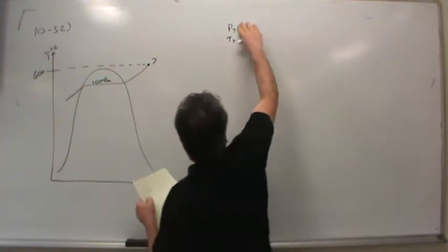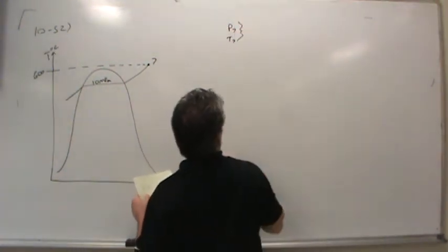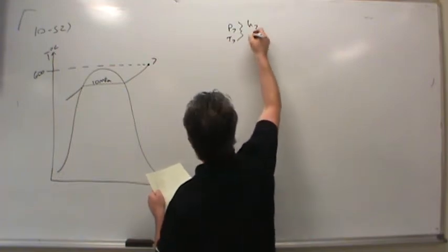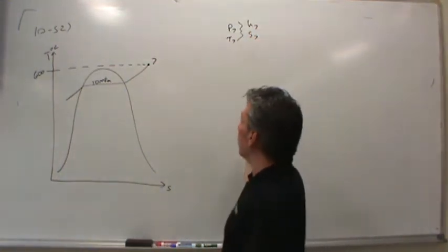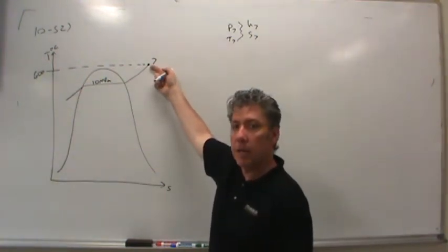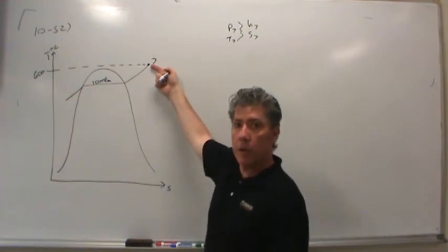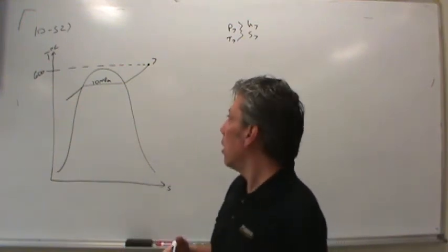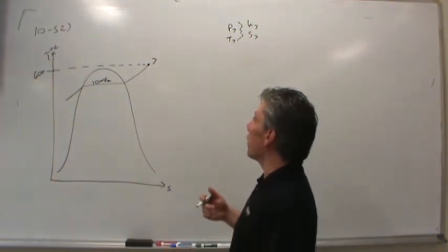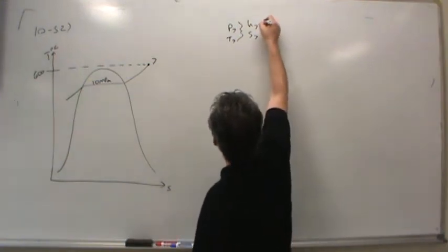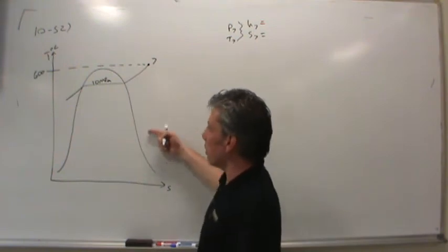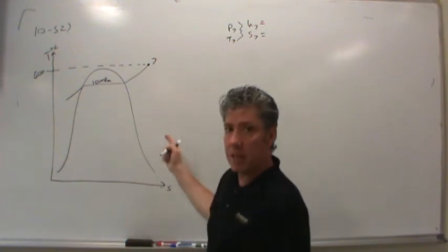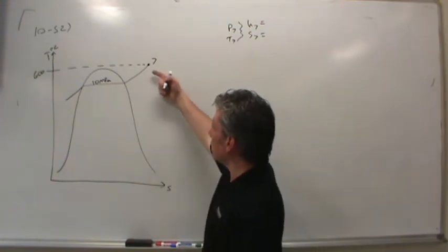Those two pieces of information together allow me to figure out things — for example, the enthalpy at state 7 and the entropy at state 7. I care about the enthalpy because it represents the amount of energy the steam has, and it will help me quantify how much energy the steam gives up as it moves through the turbine. The entropy will help me discover information about other states, such as the state coming out of the turbine at the end or as bleed steam is pulled off to go to the open feed water heaters.